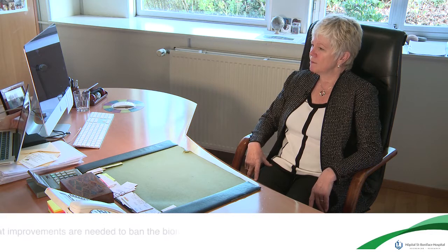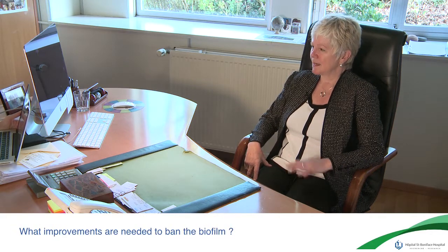So what, in your opinion, are the main improvements to be made specifically with regards to biofilm? In my opinion, the main improvements that are really needed in endoscope reprocessing occur in two areas. The first area is the cleaning, the manual cleaning step, and the need to ensure that there is an adequate detergent solution and that there's adequate brushing and adequate cleaning and rinsing done.